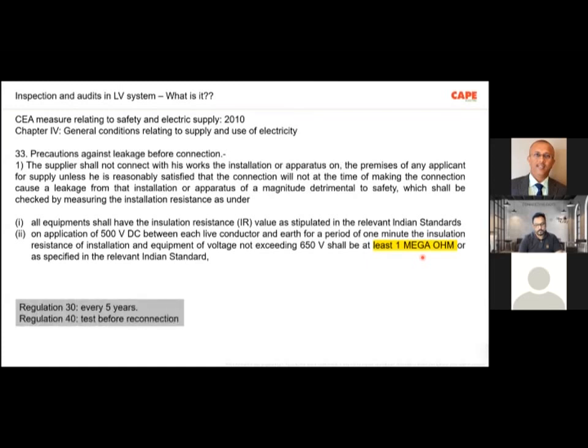And the regulation 30 says this test shall be done every 5 years. Regulation 40 says this test shall be done before a reconnection. And who has to do this test? It is for the electricity supply company. The electricity board or the electricity supply company is supposed to do this particular test.